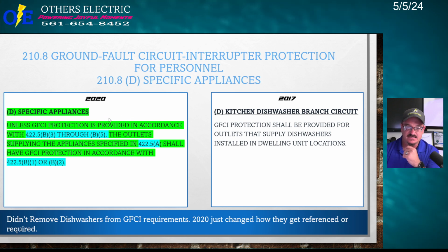Here's what it says in the 2020. D, specific appliances. What we're going to be doing is going in and out of the code. So we're going to come over here. So we're going to read this. But anyway, unless GFCI protection is provided in accordance with 422.5(B)(3) through (B)(5), the outlets supplying the appliances specified in 422.5(A) shall have GFCI protection in accordance with 422.5(B)(1) or (B)(2). So I want you to understand this. What did it not say? It did not say receptacles. It said outlets. So if these specific appliances, even if they're receptacles or not receptacles, if it's just hardwired, they have to be GFCI protected no matter what. Either way, no matter.